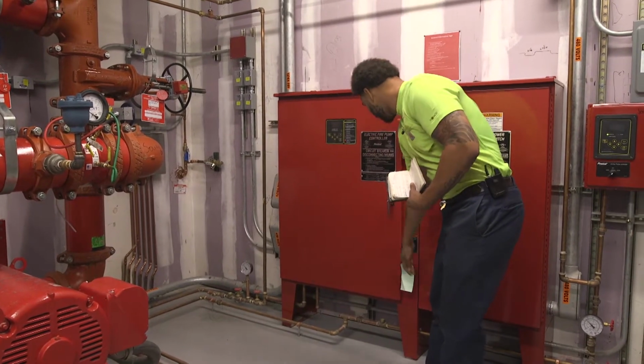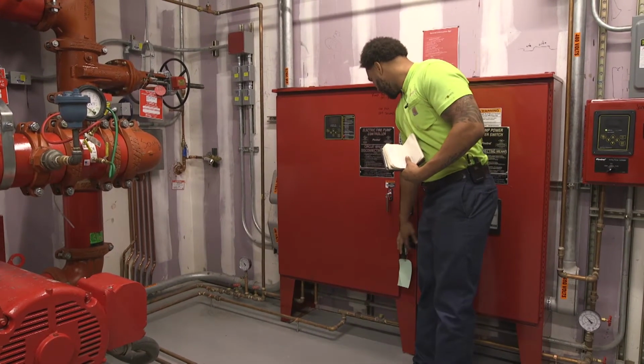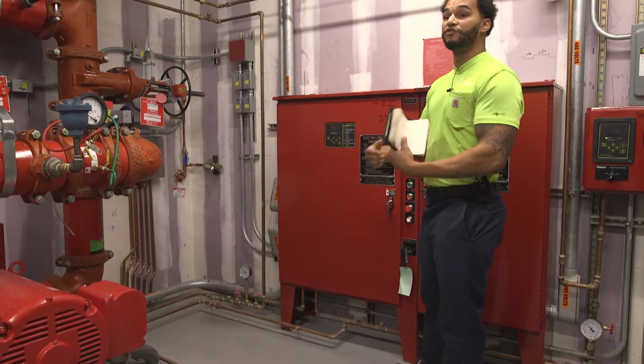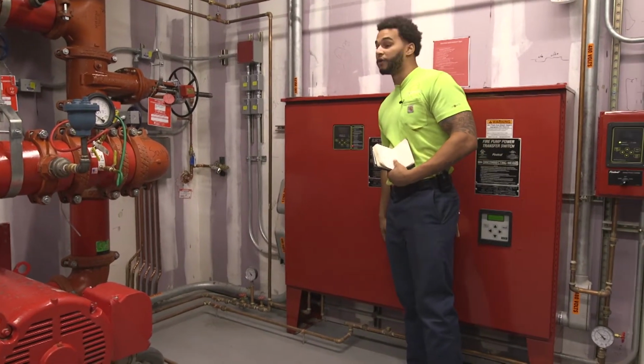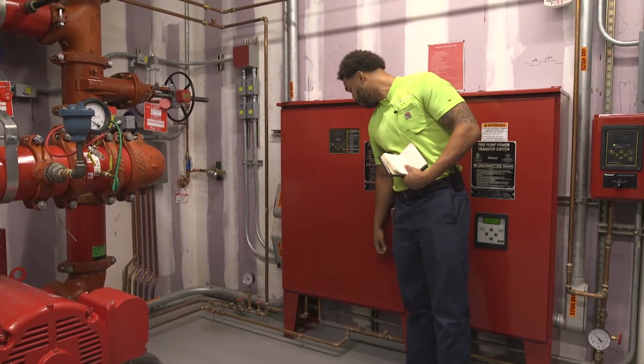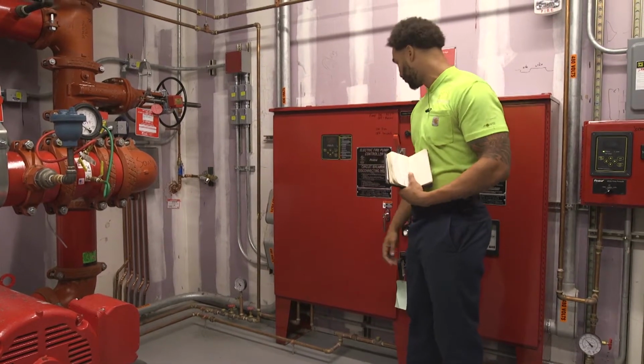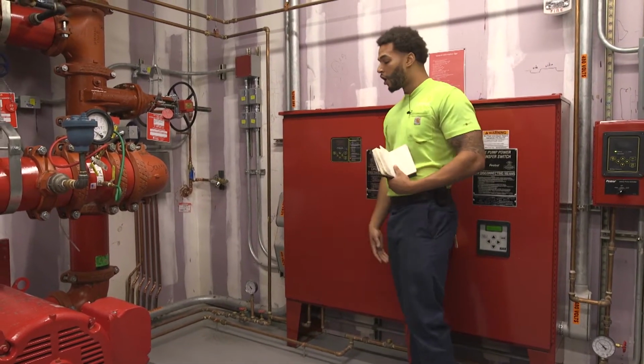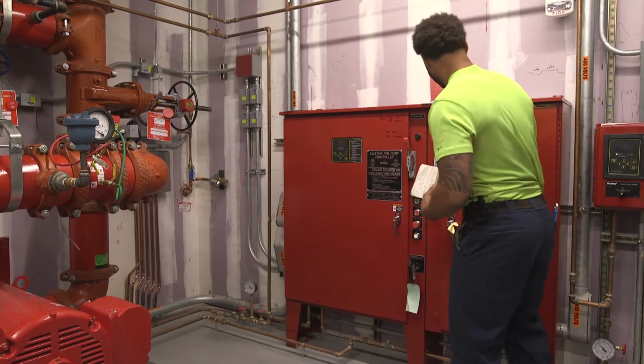Here we have our emergency run handle. By pushing this handle, it's going to, again, bypass that soft start and apply full current into our breaker here, through our contactor, and give our pump full power.